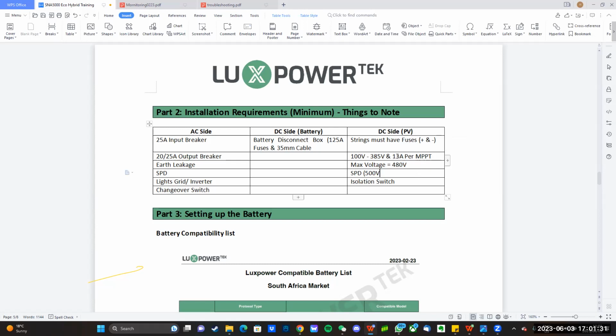I had a situation a few days ago where a client was using 550 watt panels, rated at about 13.7 amps, which is 0.7 amps over the limit. What I recommended is you bridge both connections from the Luxpower side, bridging the PV1 and PV2 ports together, positive and negative ports together. Then on the setting side, which I'll show you later, when you change the PV setting, it will combine the two so they work together as a combined 26 amp limitation. That's for your bigger panels, which is quite nice.